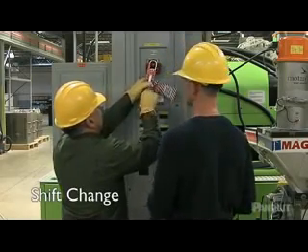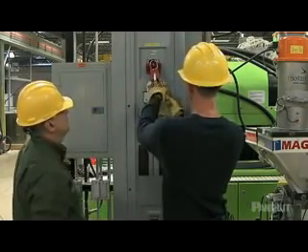During the procedures, each authorized employee must place their own lockout or tagout device on the group lockout device, such as a hasp or group lockbox. They must also remove their own device after the service or maintenance is completed. When your shift is over, leave your lock in place until the next shift arrives. Continuity is critical. Let the new shift snap their locks into place before you remove your own lock.